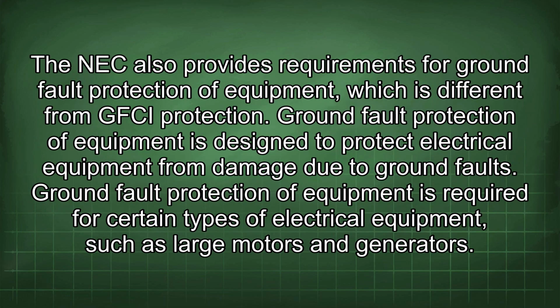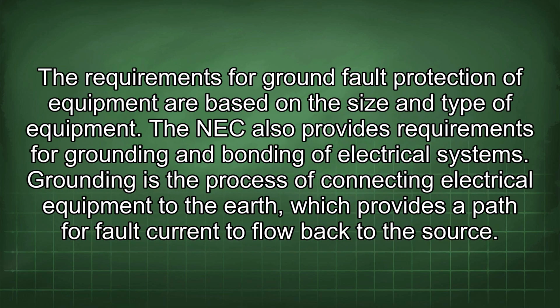The NEC also provides requirements for ground fault protection of equipment, which is different from GFCI protection. Ground fault protection of equipment is designed to protect electrical equipment from damage due to ground faults. Ground fault protection of equipment is required for certain types of electrical equipment, such as large motors and generators. The requirements for ground fault protection of equipment are based on the size and type of equipment.